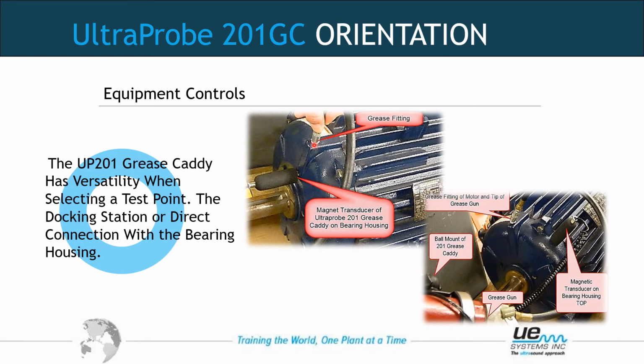Or you can mount the magnetic transducer directly to the bearing housing. Closest to the bearing is always the best. Here it is on the front end of the bell. Here it is on the top of the bell, close to the bearing.